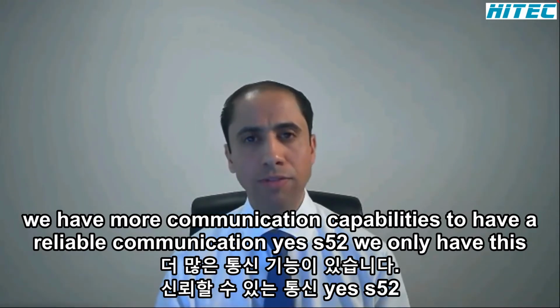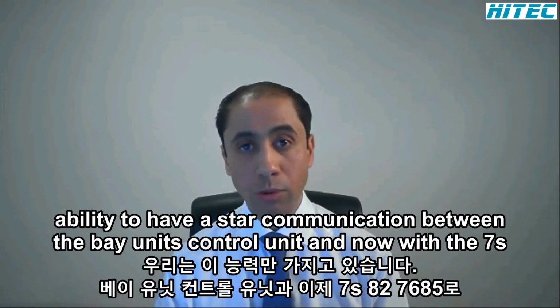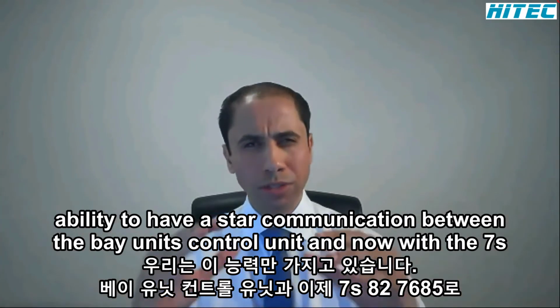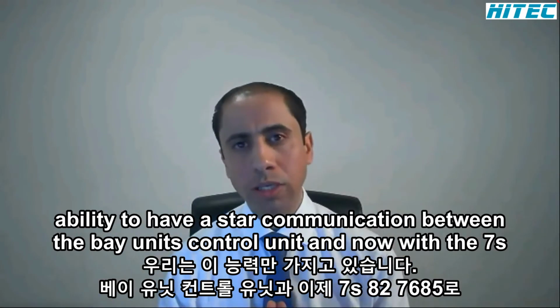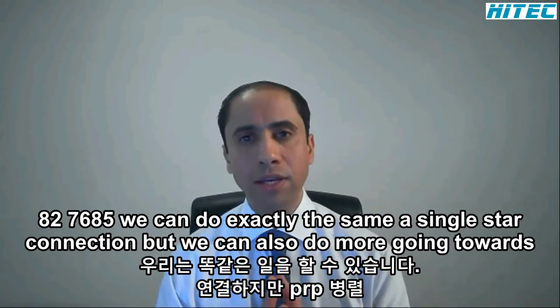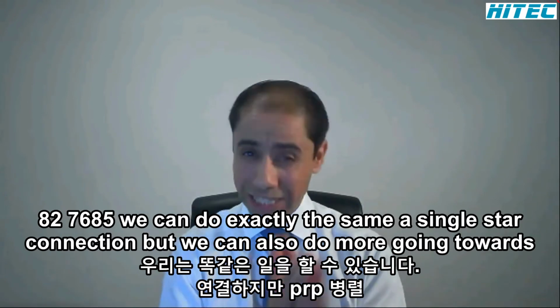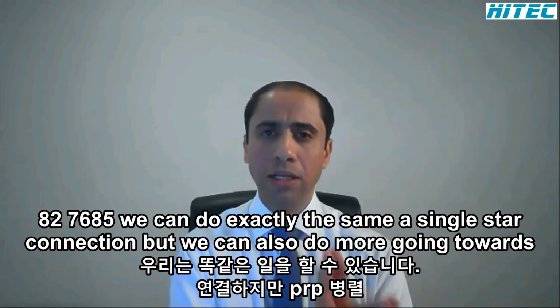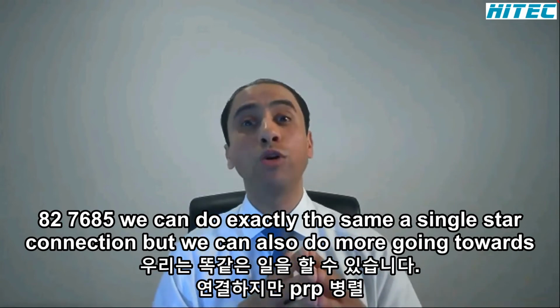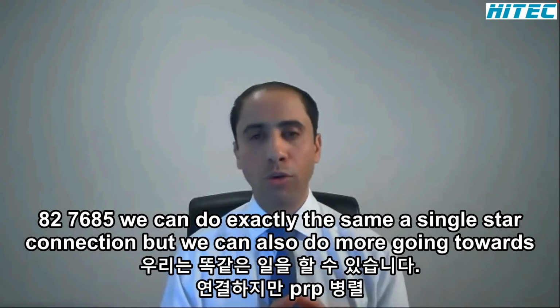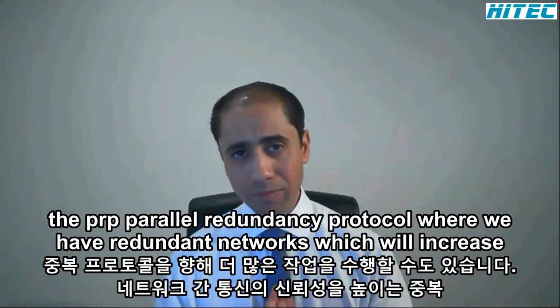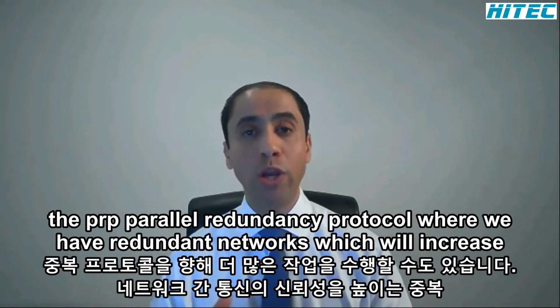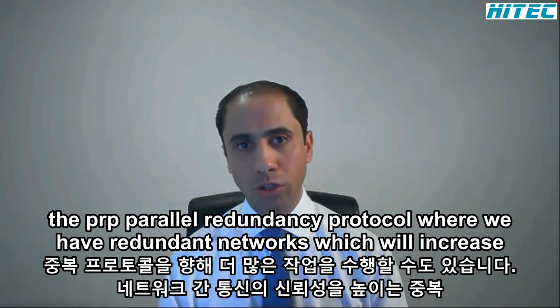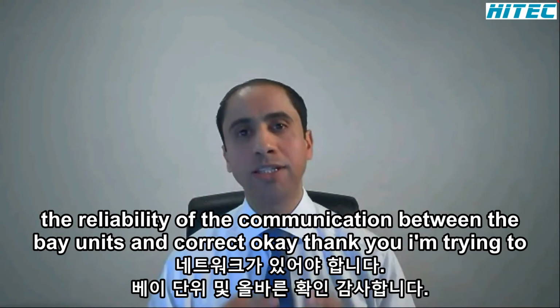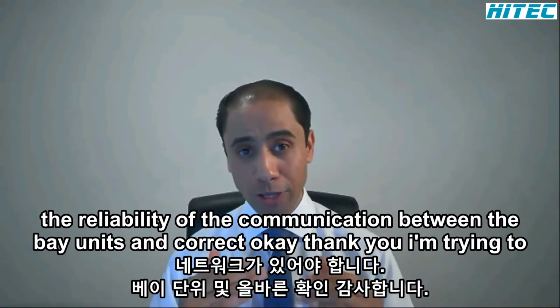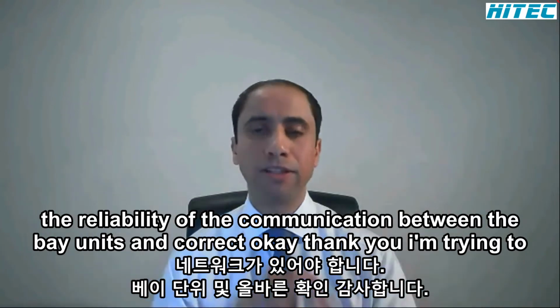Yes. With the SS52, we only have the possibility to have a star communication between the bay units and the central unit. And now with the 7SS85, we can do exactly the same, a single star connection, but we can also do more going towards the PRP, parallel redundancy protocol, where we have redundant networks, which will increase the reliability of the communication between the bay units and the central unit.